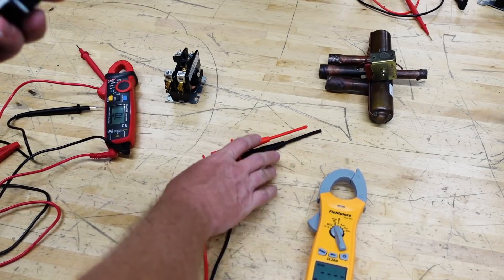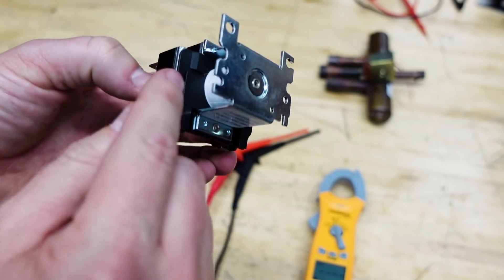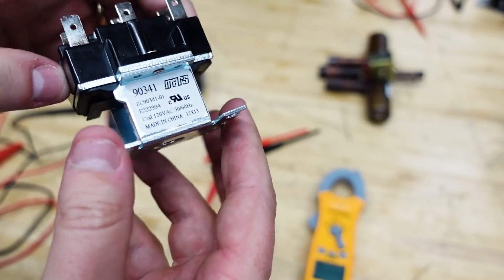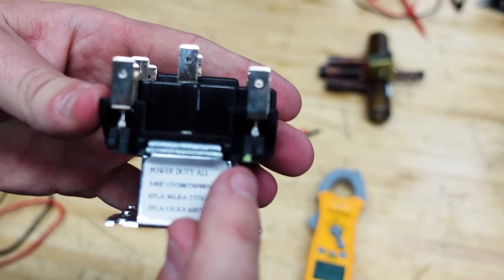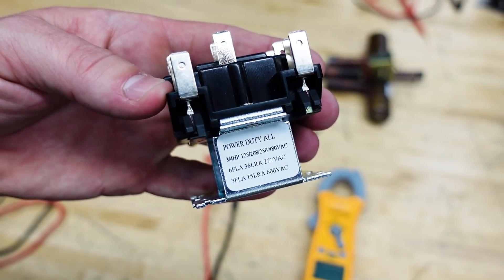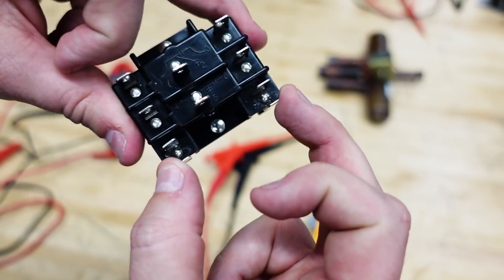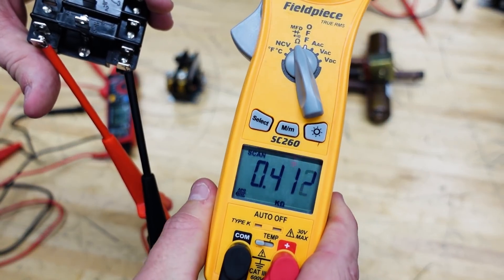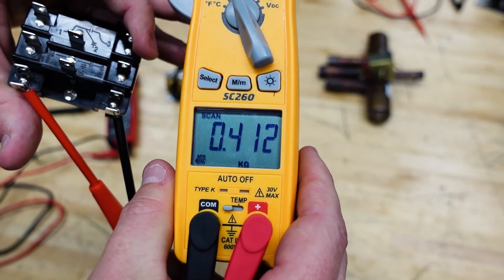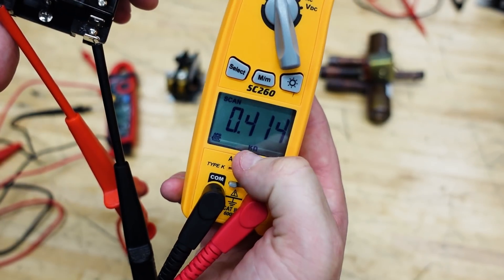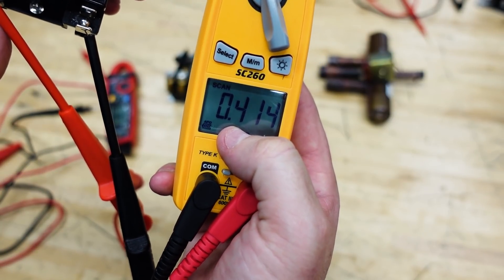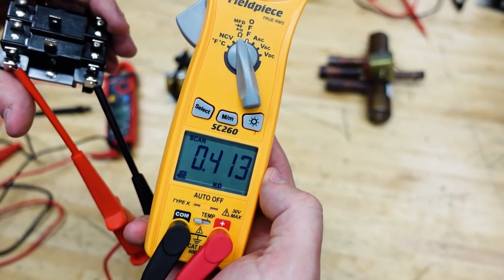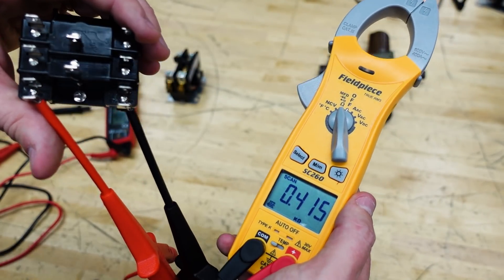Okay, but we're going to look at the coil again. So here we've got this, it's covered in this white plastic here. But if you look really carefully, you can actually see where the little copper wire runs in and then it connects to these points right here. You can actually see the copper running up through this little channel to both of these connection points. And so these are the points that are the coil. Because the coil is a load, it's going to have a measured resistance. So let's see what we got. Wow. On this, it's auto scaling to 0.4 kilo ohms. So this is measuring at, if we move the decimal over from K ohms, thousands of ohms, we can see that this is actually measuring, what would that be? That would be 416, 414 ohms. Now that seems really high compared to the other coil. But again, we would have to compare this against another 90341, another similar relay in order to know.